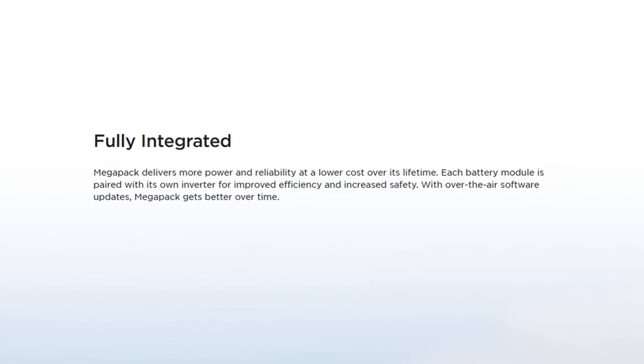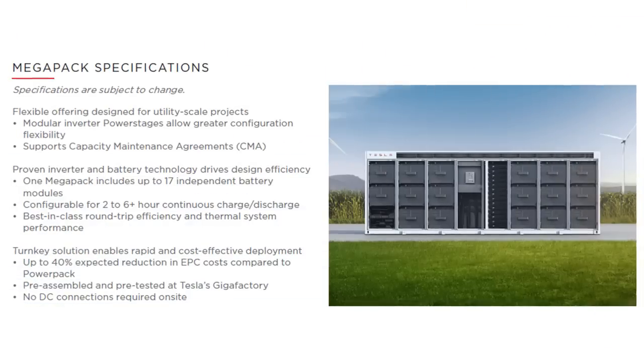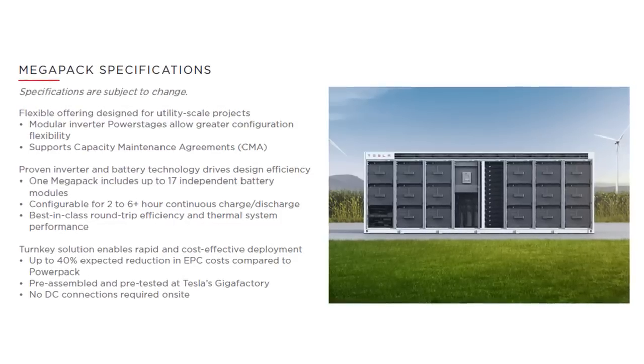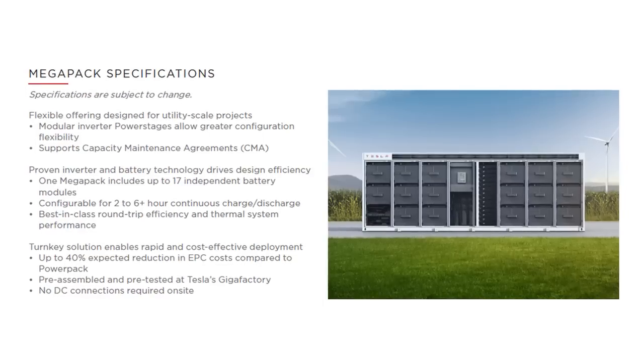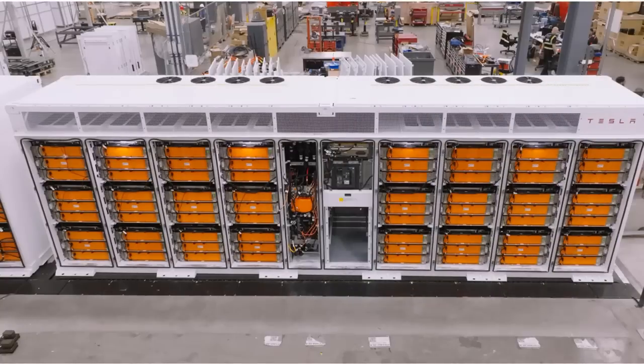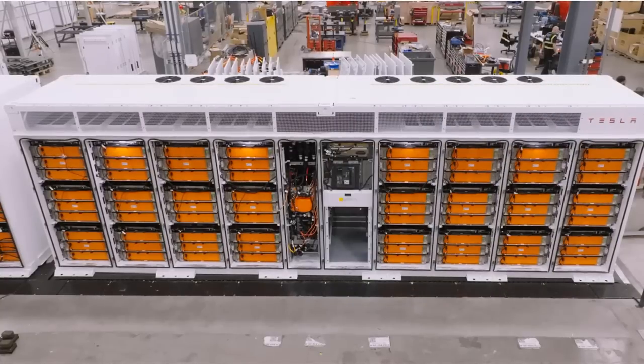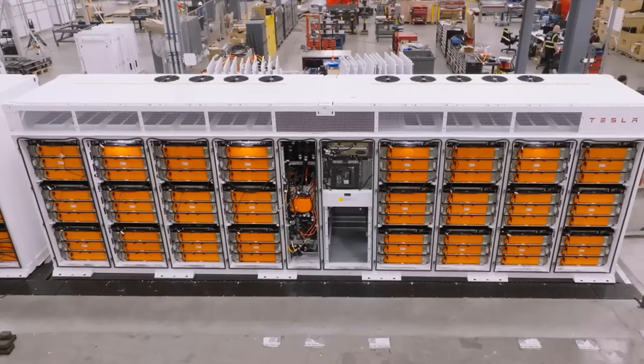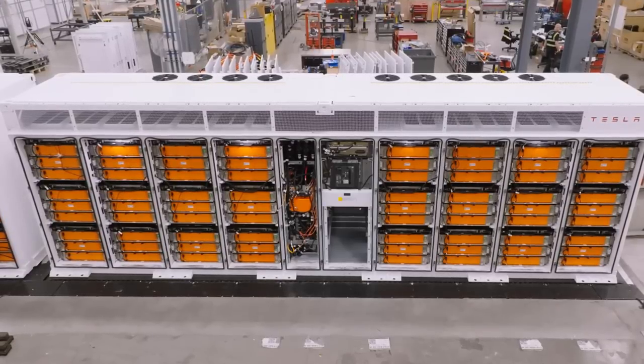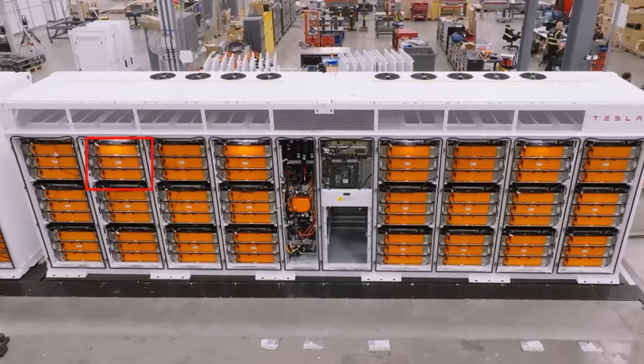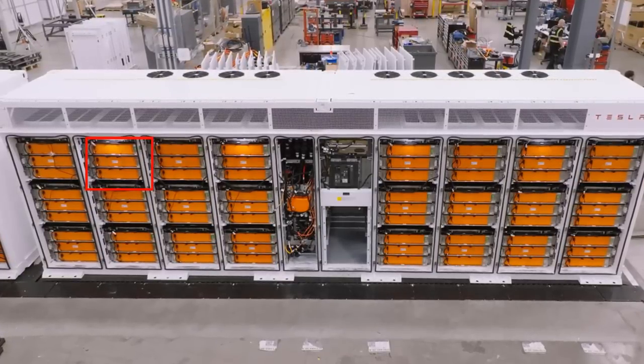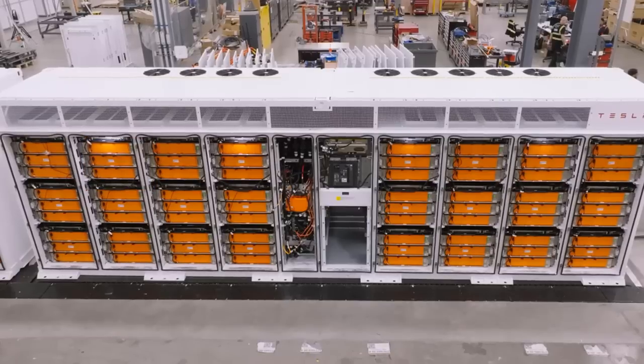The previous Megapack had 17 independent battery modules, and based on a recent photo Tesla released of the internals of the new Megapack, it looks like there are now 24 modules, meaning 24 inverters. Each module appears to be made up of a stack of 3 battery packs, meaning there are 72 battery packs in total used to form the Megapack.